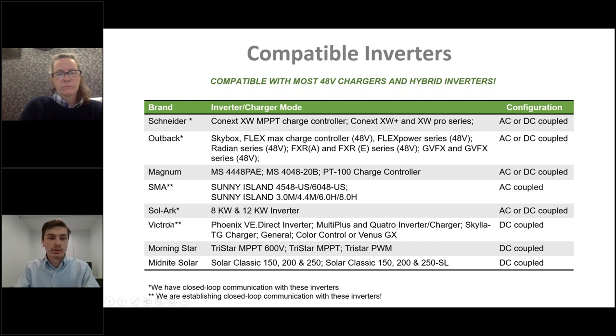You'll see here with the asterisks that we have closed-loop communication with some of these inverters, like Schneider, Outback, and Solark. We're currently doing testing to establish closed-loop communication with the two-star inverters, the Victron and SMA inverter series. So first determine which inverter you're going to use, and then how you're going to set it up - are you using this in closed-loop communication, are you AC or DC coupling this, or are you going to use it in open loop communication?